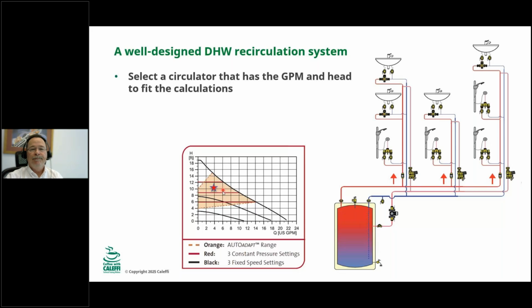Yeah, I'll just add that this technology seems like it's getting better every day, and the circulator manufacturers have a lot more programming choices too. One of the things to double check is if these recirc pumps are operating on some sort of temperature-based setting. We'd want to make sure that doesn't conflict with what the temperature-based thermal balancing valves are trying to do, because you can have two different hands on the steering wheel there. So if you're using a manual or an automatic balancing valve, then a temperature-based setting might be the right one. But you maybe want to use a pressure setting if you're using thermal balancing valves like Kevin's showing on the slide here.